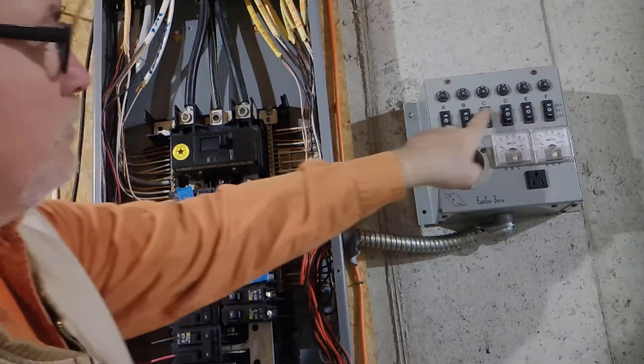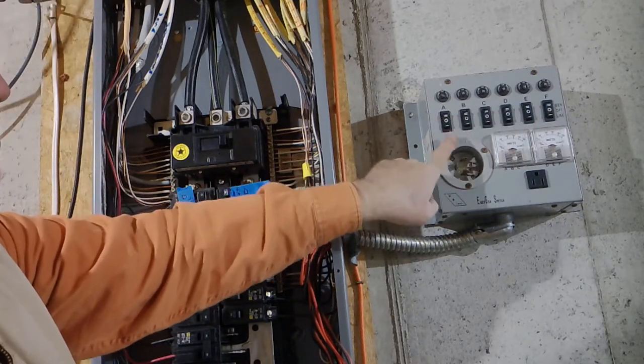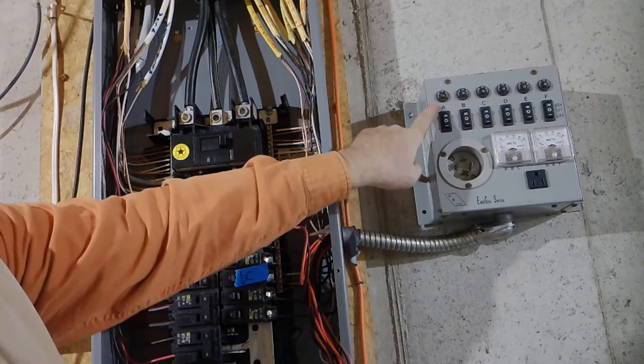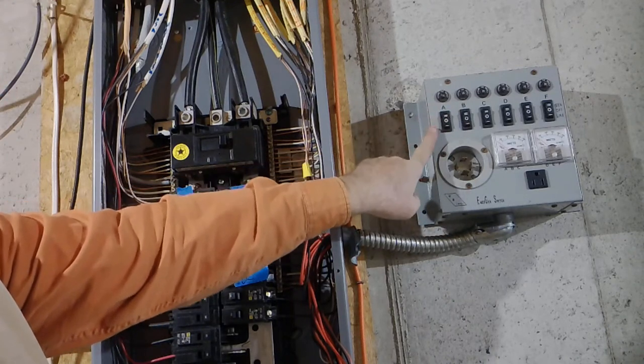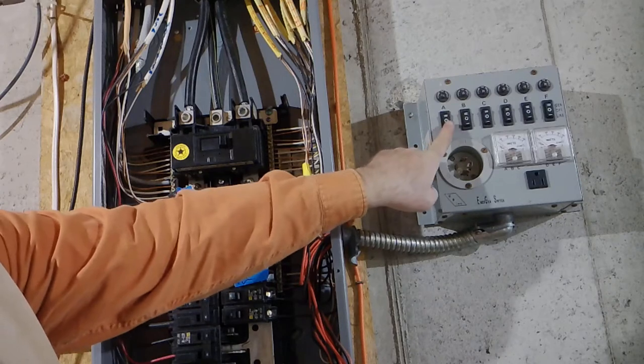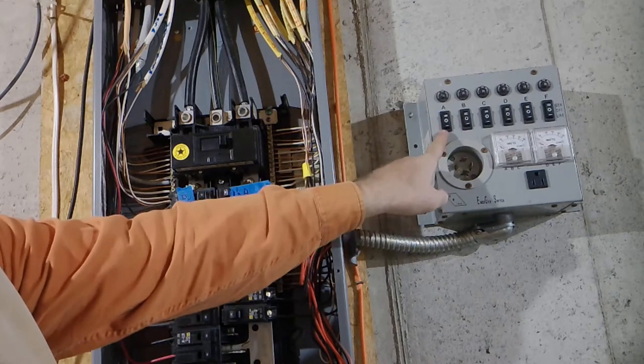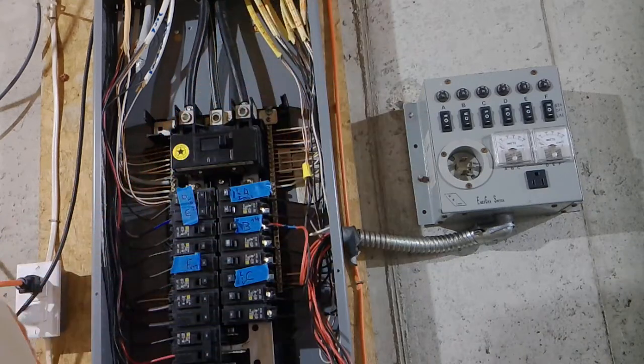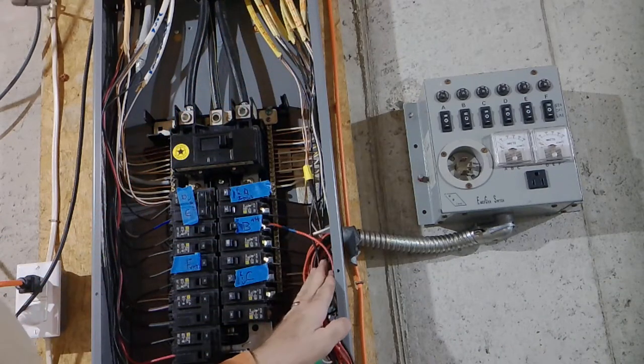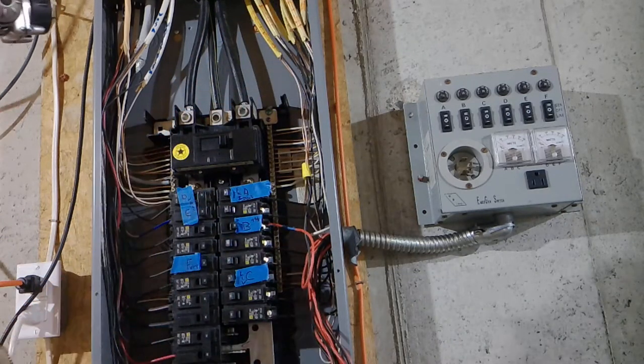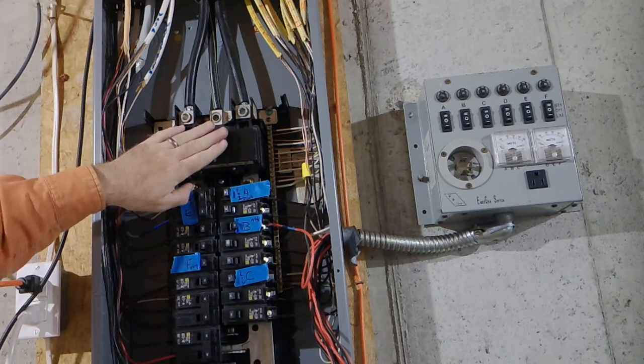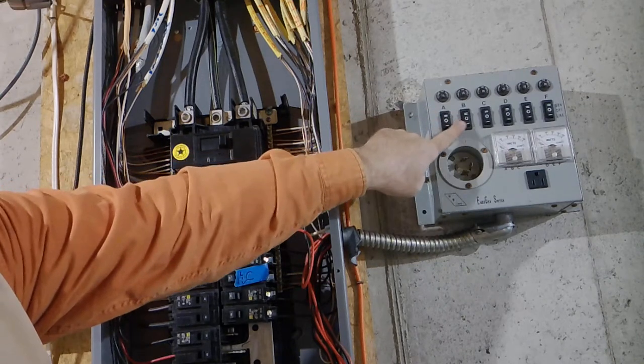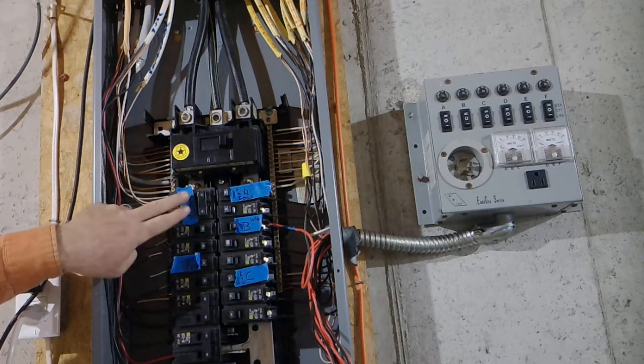So as I do that, I make sure all my fuses are in the neutral position. Off. I don't have it on the line. I don't have it on the generator. After I get done wiring this up, I can turn that on. That will be line so the circuitry will be live and everything that you're feeding will be running. When the power goes out, you don't have to shut this off. You can leave it on. You just switch these to generator mode.